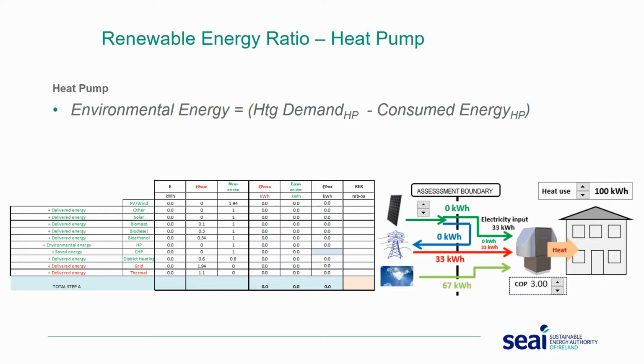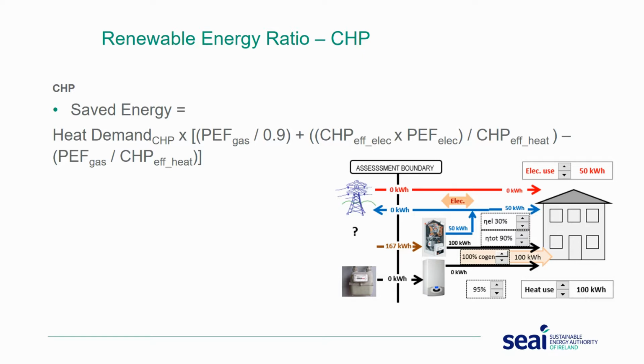So just to make you aware of that, it's likely that heat pumps will be used more regularly now. The CHP, again, is similar to what was there before. We are allowing for the renewable contribution from CHP to be the saved energy, so the primary energy we have saved from installing the CHP. What we do is calculate the equivalent of a gas boiler and grid electricity, minus the amount of energy that goes into the CHP, and that is the saved energy, which is regarded as renewable under the building regulations.